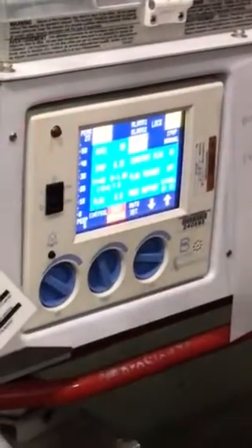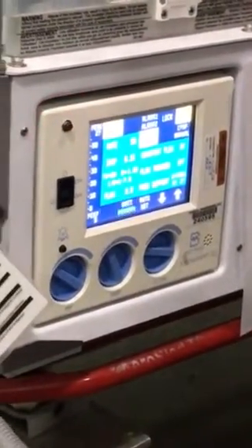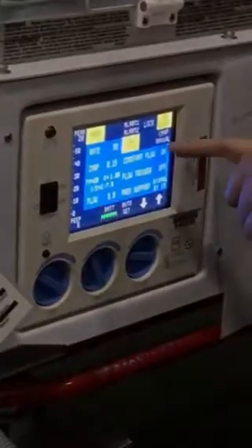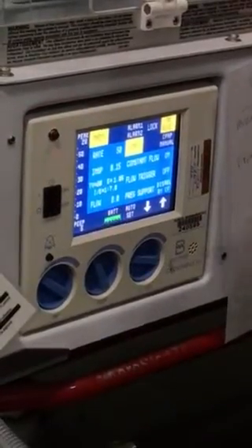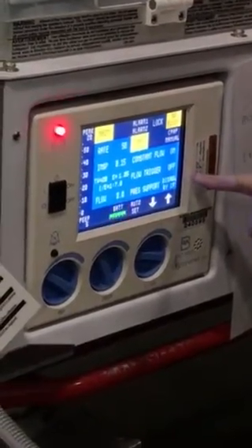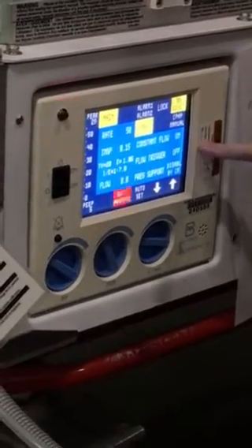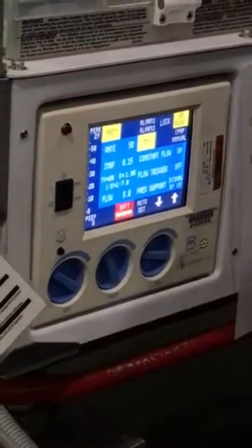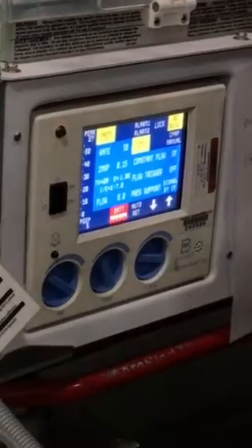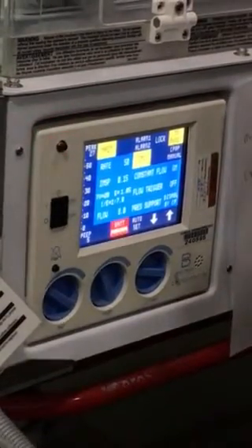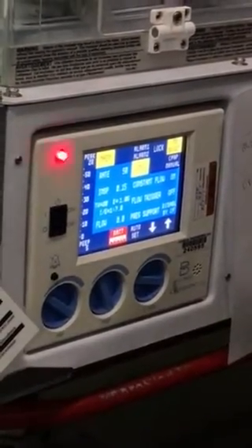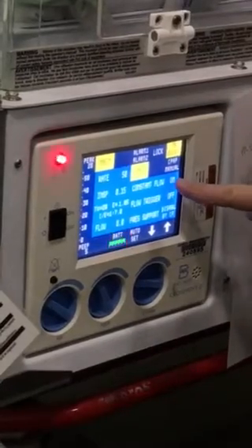So if you hit the main screen, now we're going to touch everything in. This is actually in CMV mode at the moment, which makes your flow trigger off, and you don't have any pressure support. So you wouldn't need this flow sensor in for this. This is regular old time cycled pressure limited ventilation. Okay, so when we put this in, we want to switch it over.